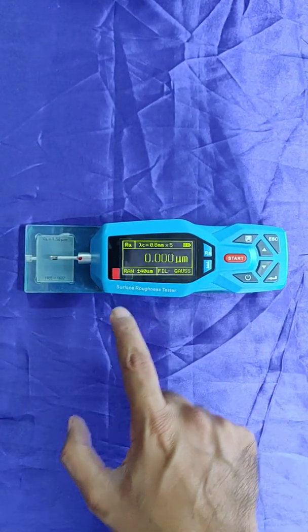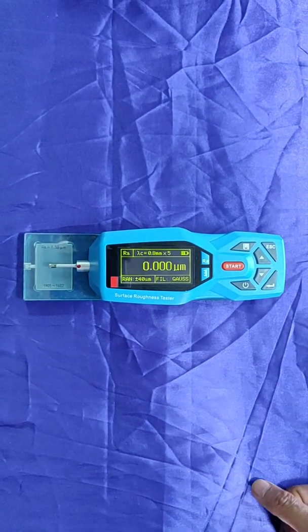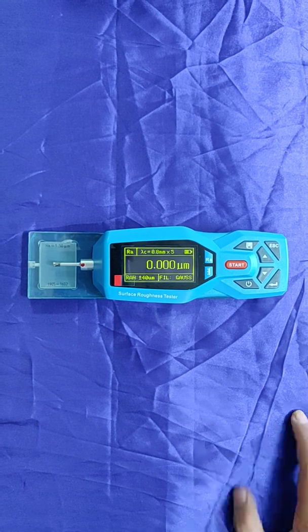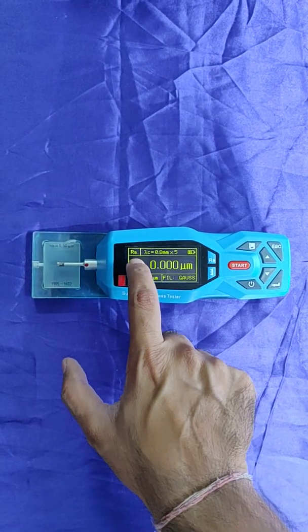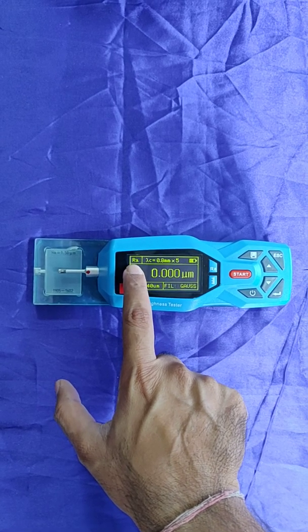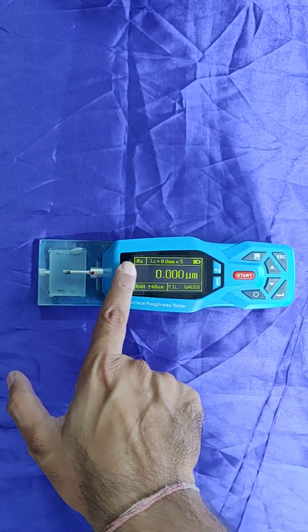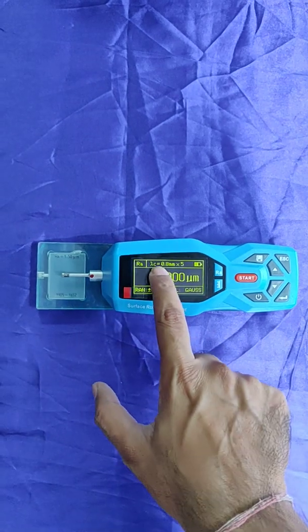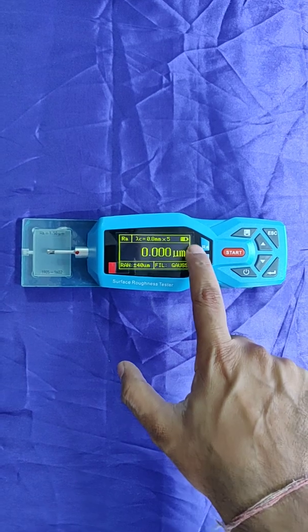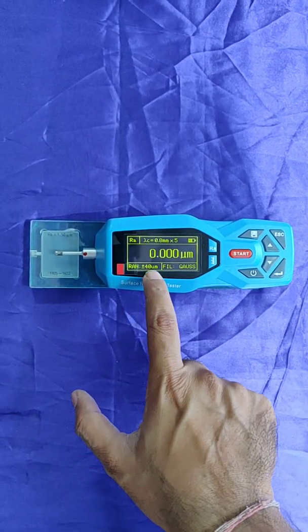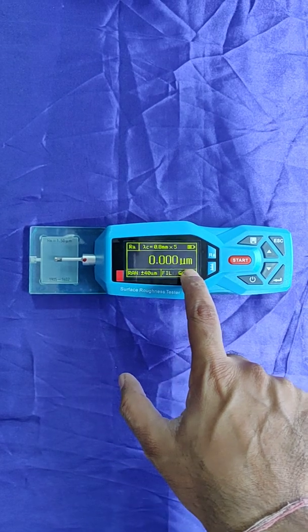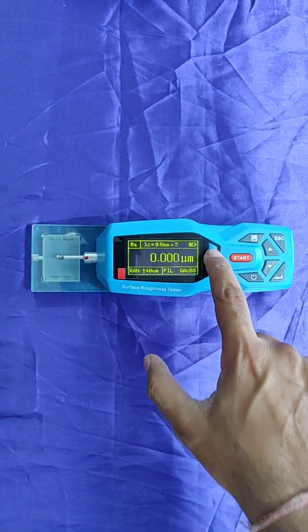The device is TR200 Plus. Now this is the main display. This is Ra. We have four values: Ra, Rz, Ry, Rt. The major value we require is Ra. The length of the measurement is 0.8 into 5 times. This is the battery, this is the range, and this is a filter, and this is the reading in microns.